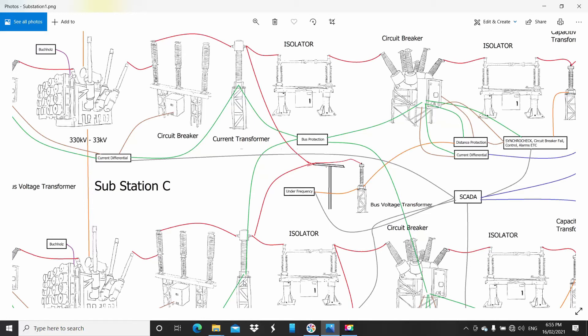That system is called load shedding. You'll often see when there's not enough power in the system, the power companies had to load shed. It's based on frequency. They'll drop so many megawatts of energy until the frequency gets up to a stable position, because if it goes too far they can't control the network properly and it'll collapse.